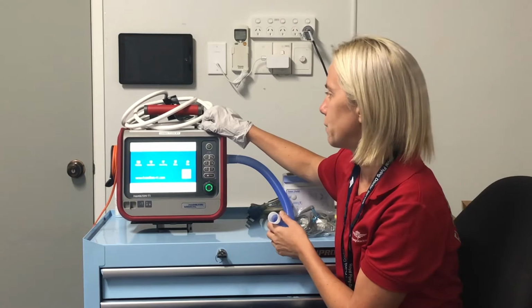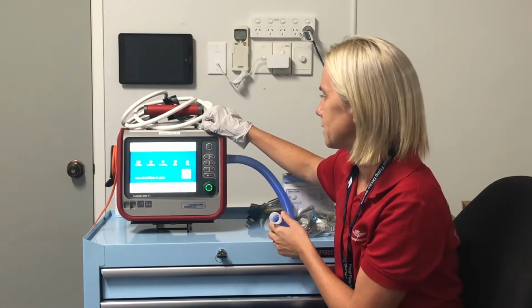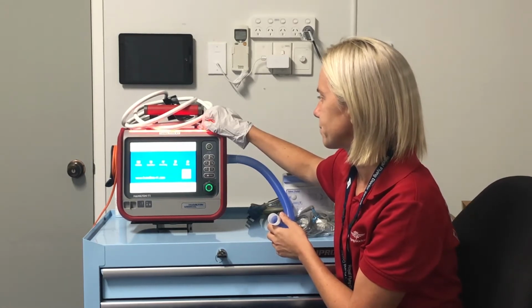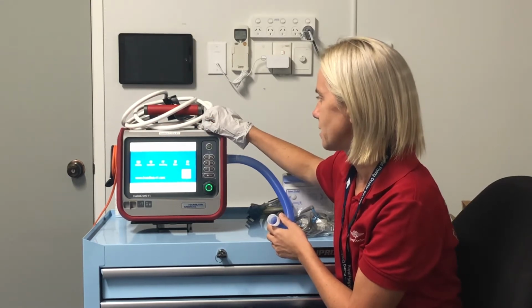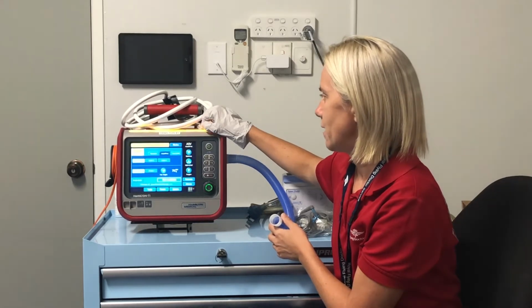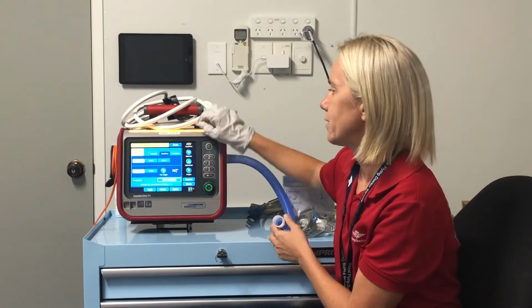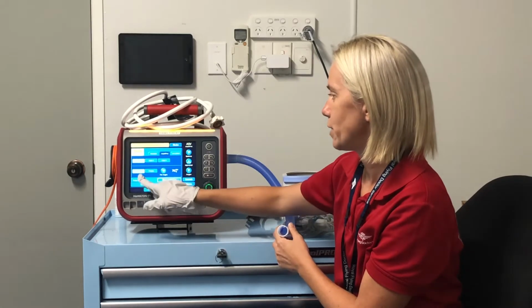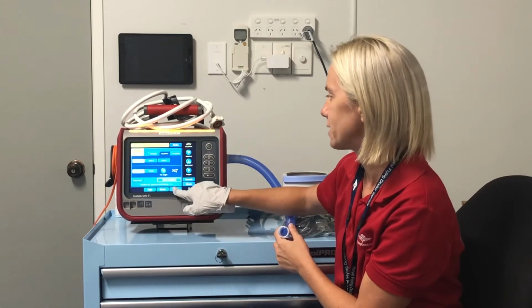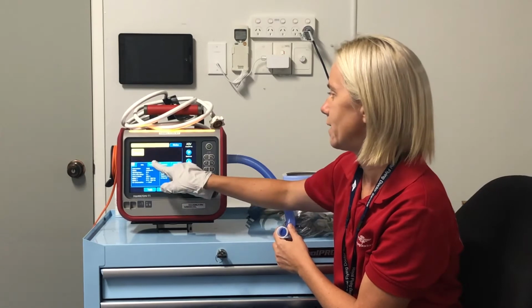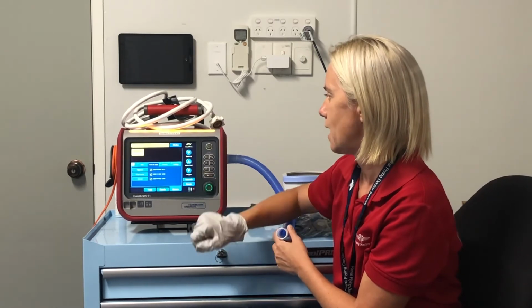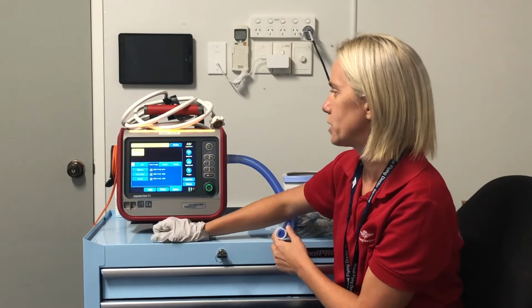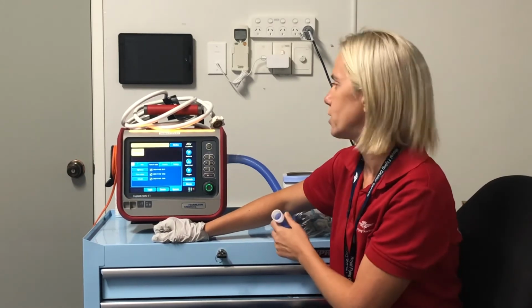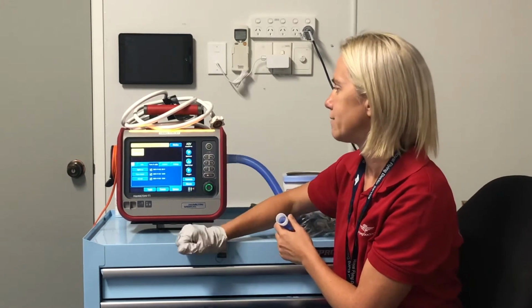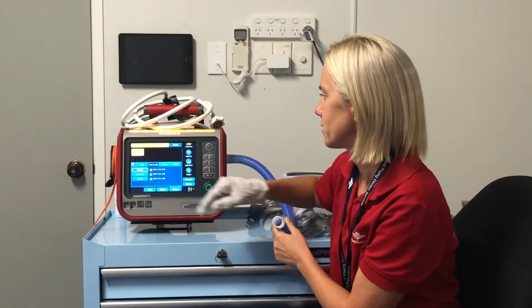So it'll do its own pre-op checklist. So we'll just wait for that to do that. And then once it's on the front screen, you can either do the pre-op check that way with the pre-op check button, otherwise you can go to system, and then there's test and calibration. And from there, we just want to do the top one, which is called the tightness test. The machine does talk you through it, but generally you'll need a gloved hand, so what we do is press tightness.